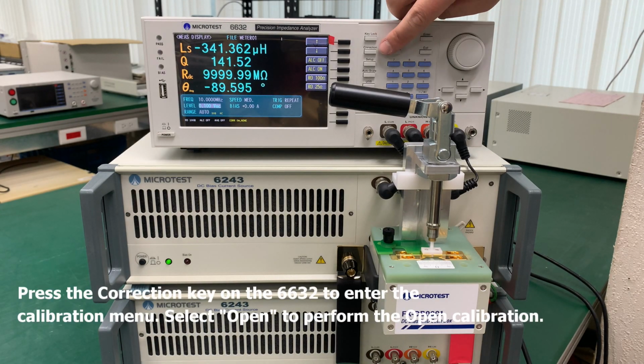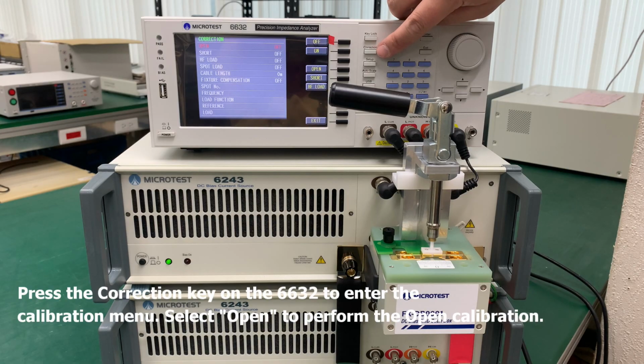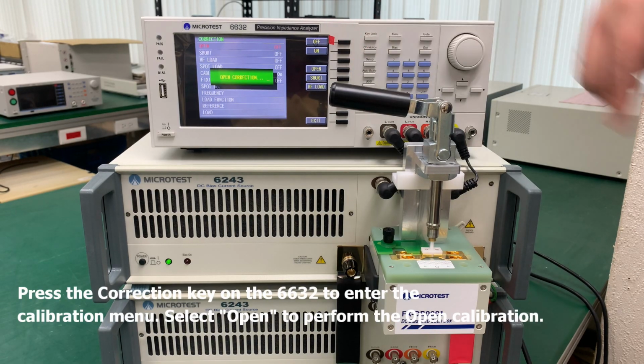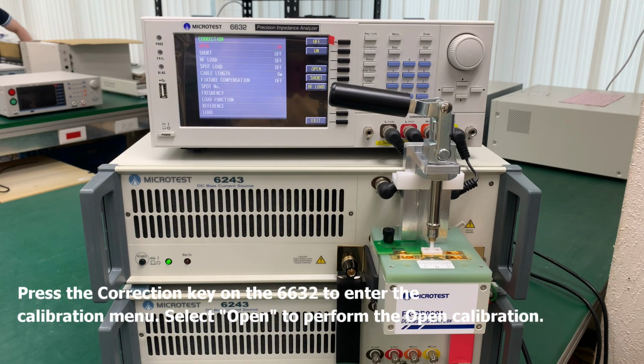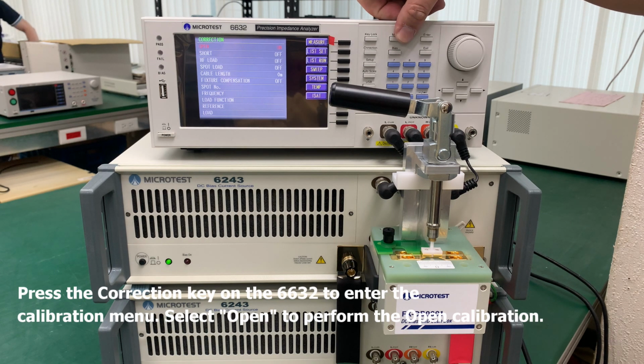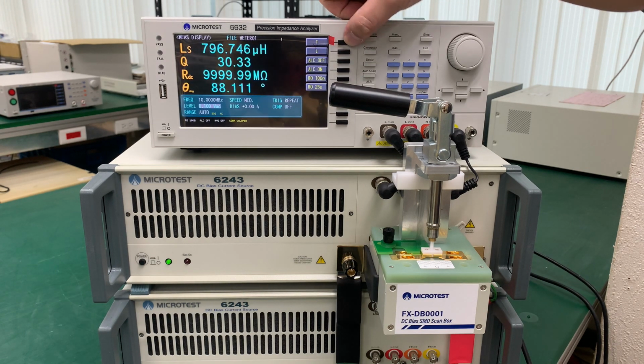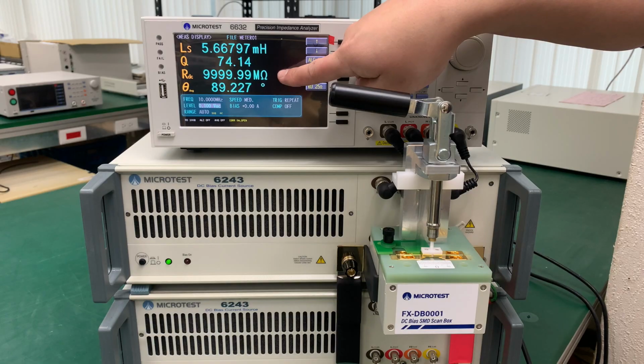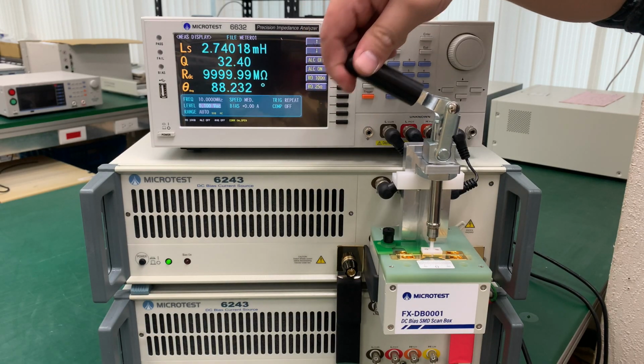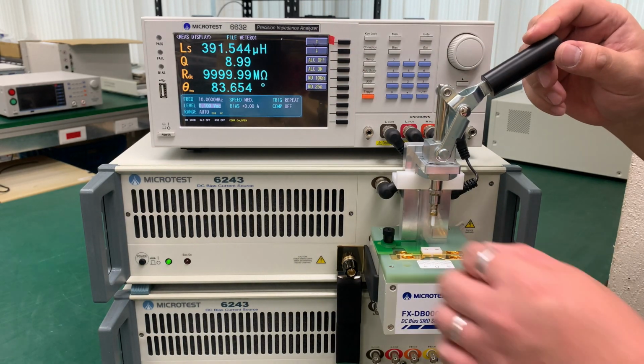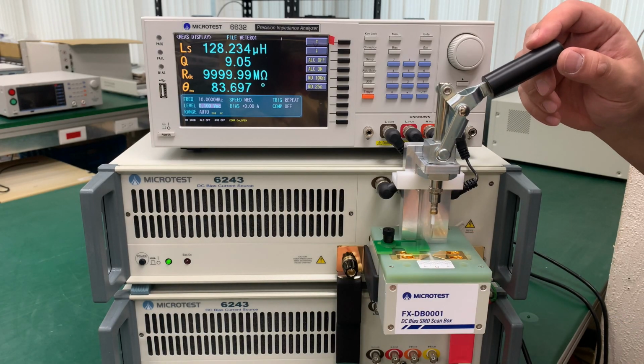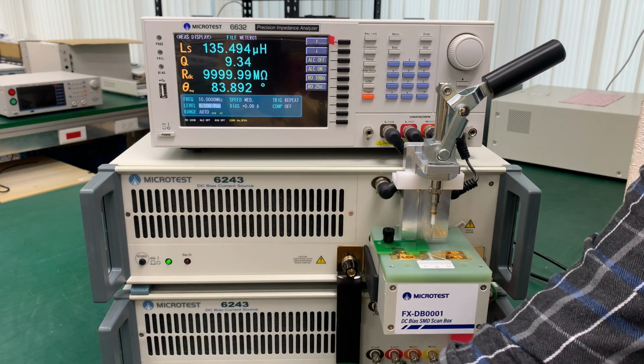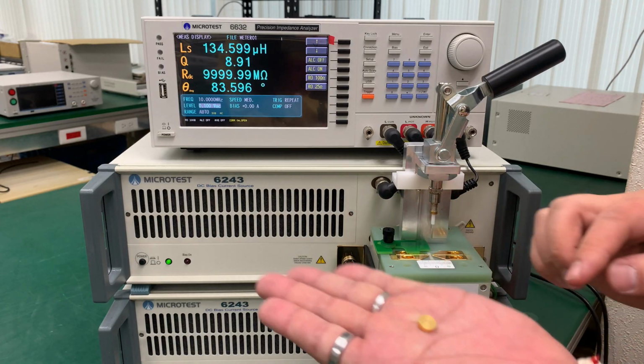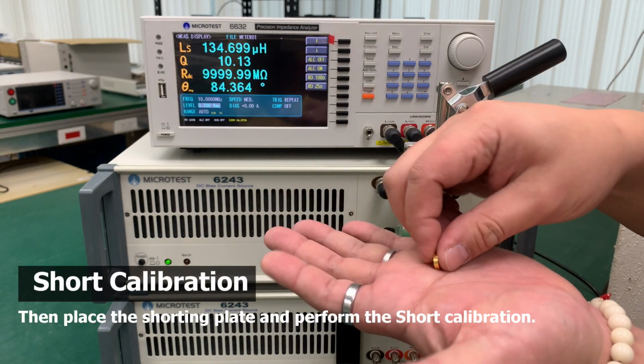Press the correction key on the 6632 to enter the calibration menu. Select Open to perform the open calibration. Then place the shorting plate and perform the short calibration.